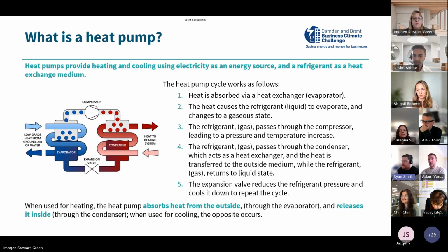So what is a heat pump? The easiest way to describe it, as you've probably heard before, is that it acts like a reverse fridge. Heat is absorbed via a heat exchanger. If you think of an air source heat pump, it extracts heat from the outside air. That heat causes a refrigerant liquid to evaporate and change to a gaseous state. This passes through the compressor, leading to an increase in pressure and temperature, then returns to a liquid state and passes heat to the space.